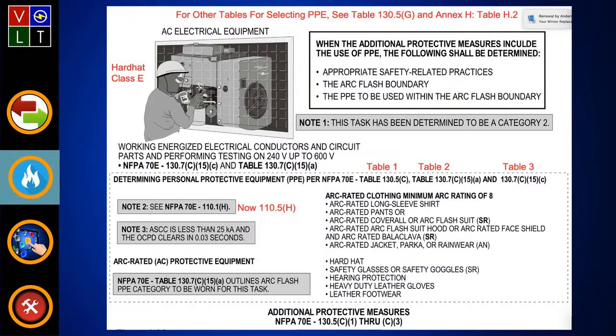Now, if you want to use the tables, we have 3 methods. If you look at the very top, we can go to our table 130.5G. And if you're 12 calories or less per centimeter squared, the equipment's listed and the equipment that you have to wear, clothing and all. If you're above 12 cal, then table 130.5G will list all the equipment that you have to use and all the clothing that you have to wear. But the main thing that the table's telling you is what are the appropriate safety-related practices you need to use to perform the task?